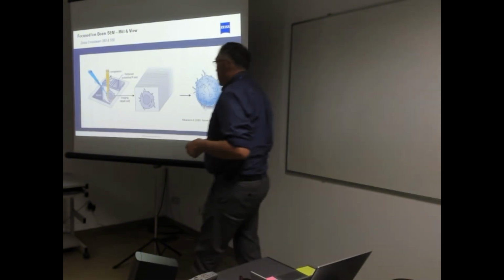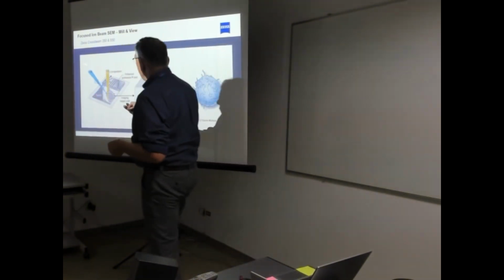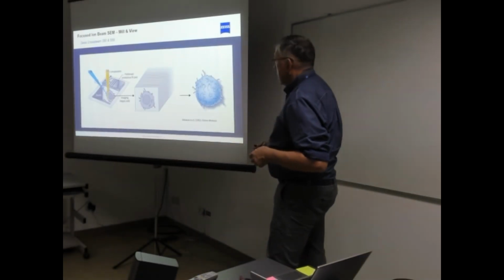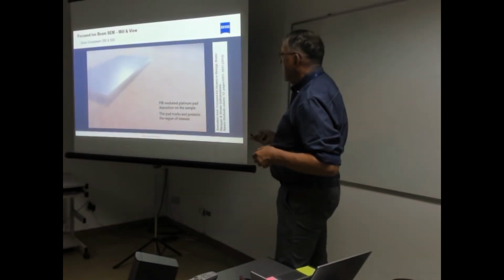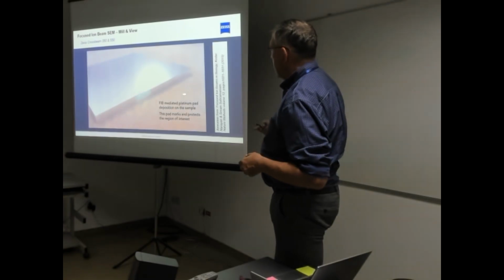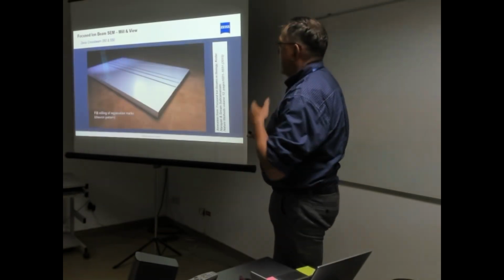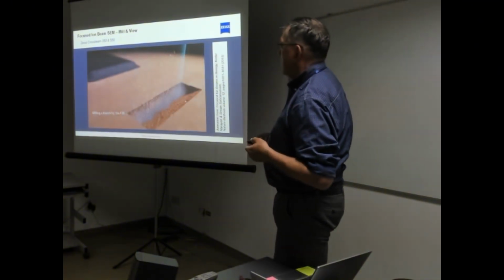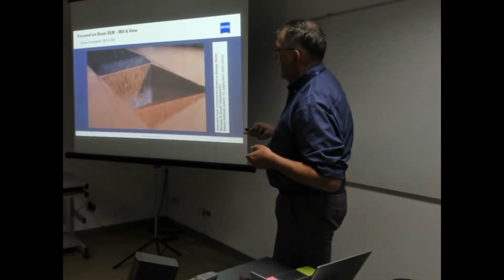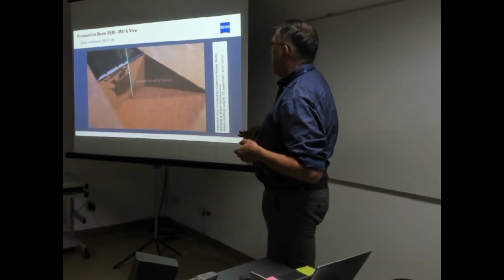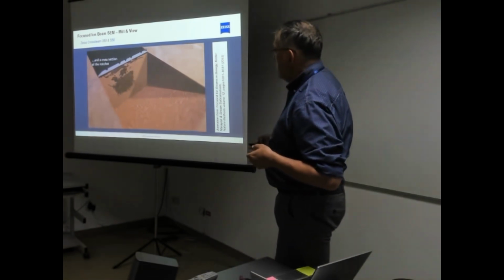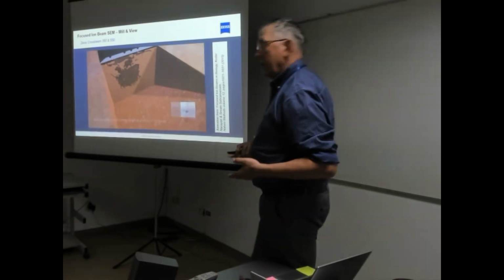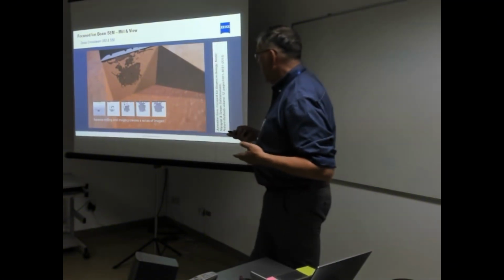The general purpose here is that you have not only the beam for imaging on the system, but you also have a focused ion beam which ablates material from the sample. And this is shown in this movie. We have to put a plate of metal on the sample as a guide for the knife, with some kind of structures which tell us how far we cut in the sample, and the carbon layer which we add to get the contrast. Now this ion beam is in action, takes material off the sample, polishing the sample, and then we take an image of this freshly created surface, and then we repeat this process, and in such a way we get information about the volume in here.